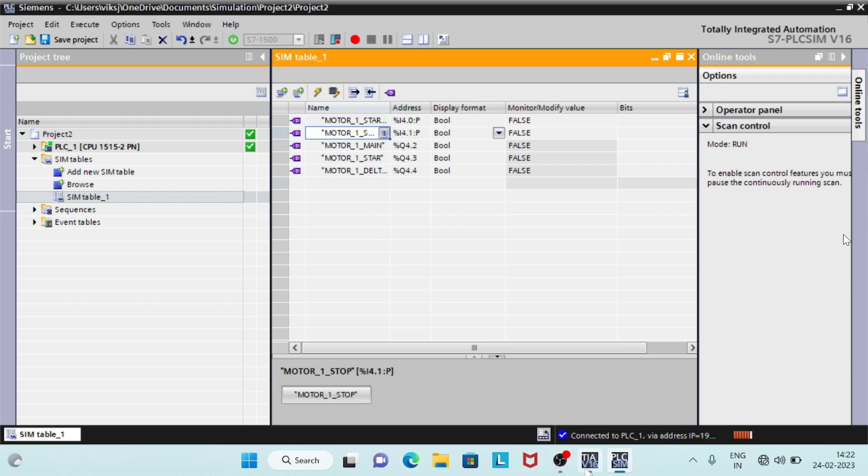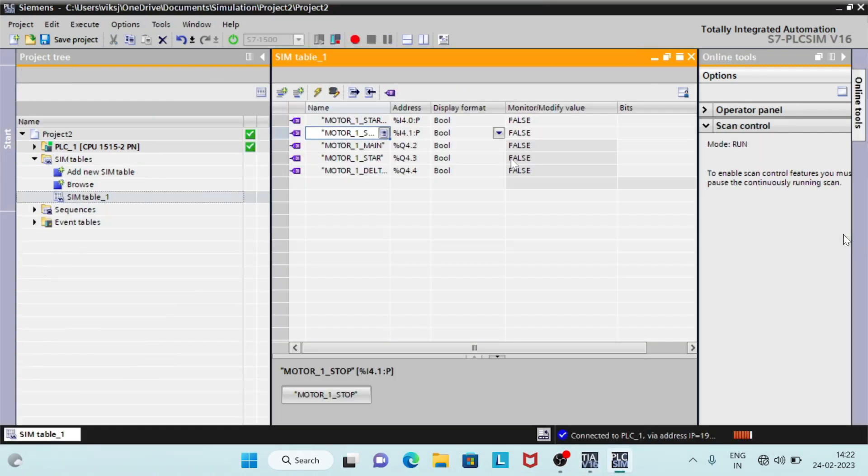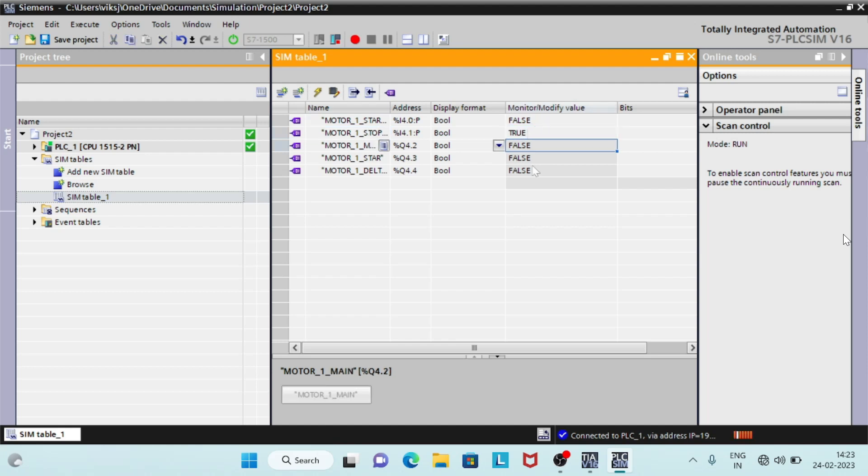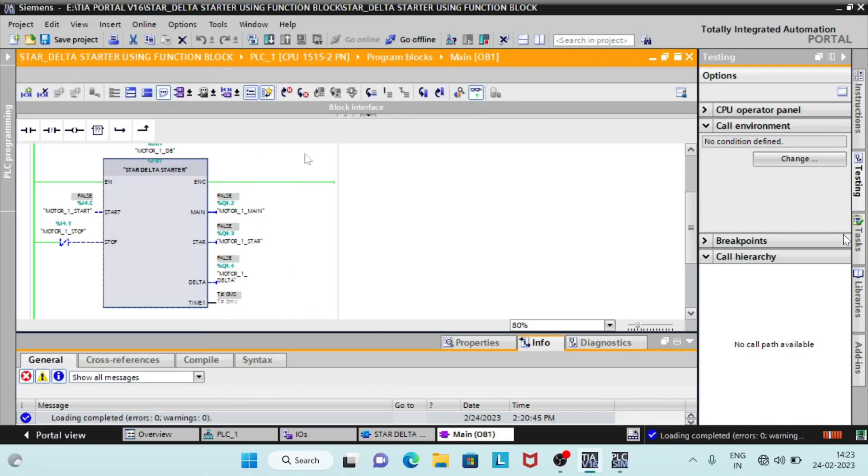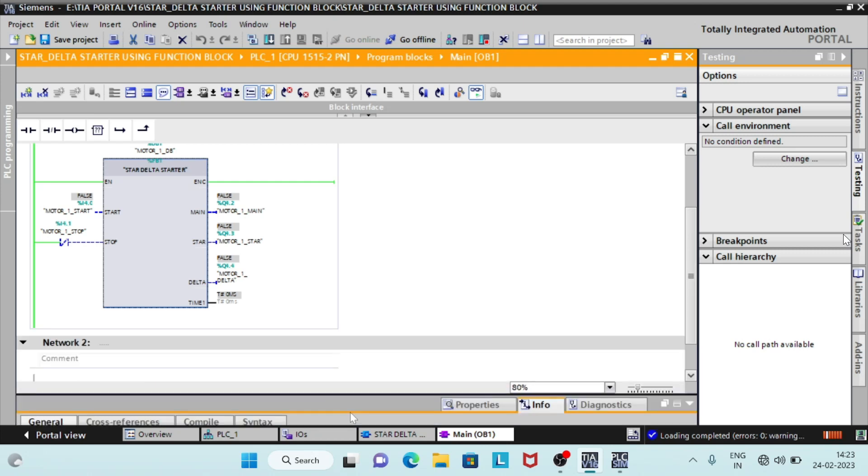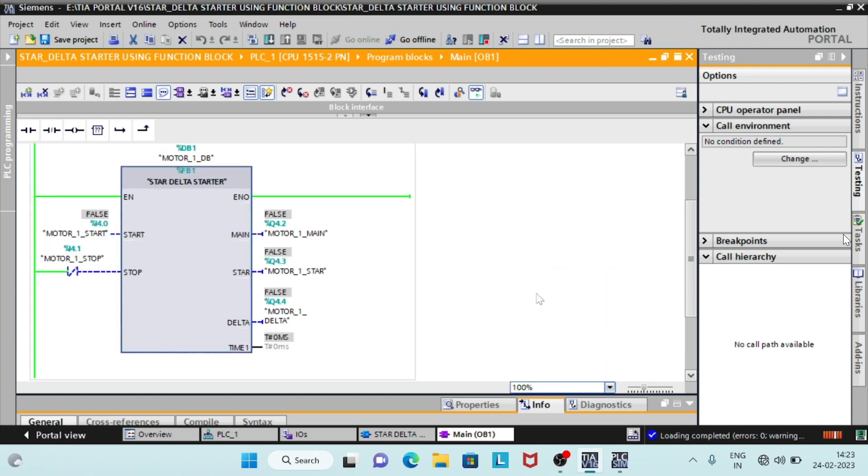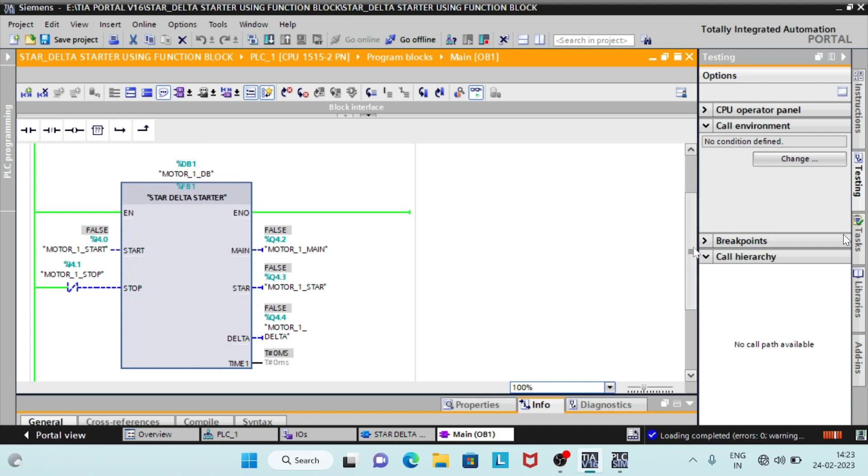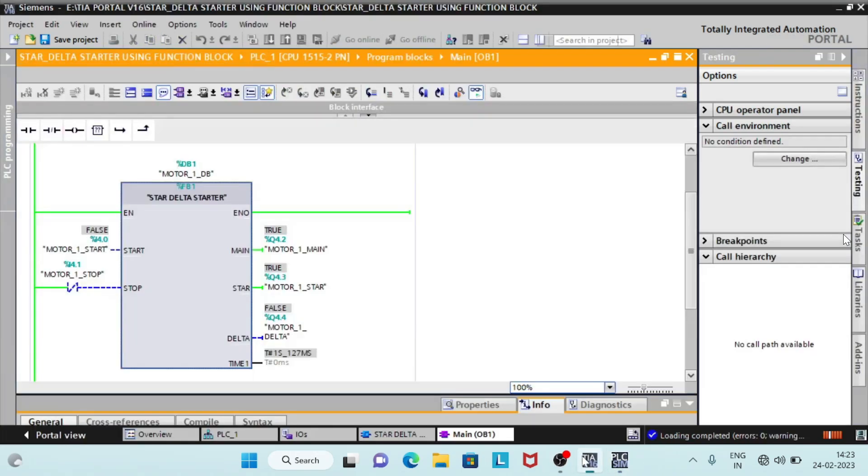In PLC SIM, modify motor 1 stop is true. As we click on Motor 1 Start, main and star coil will energize and timer will start. After the preset time of 18 seconds, star coil will be off, and delta coil will be on.